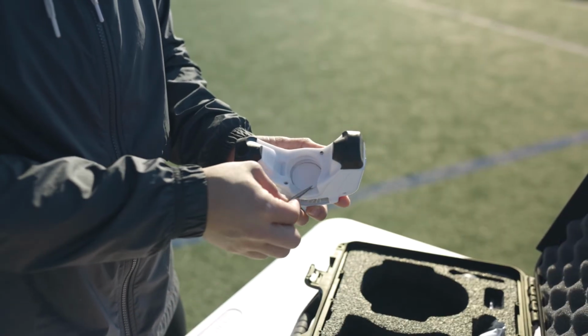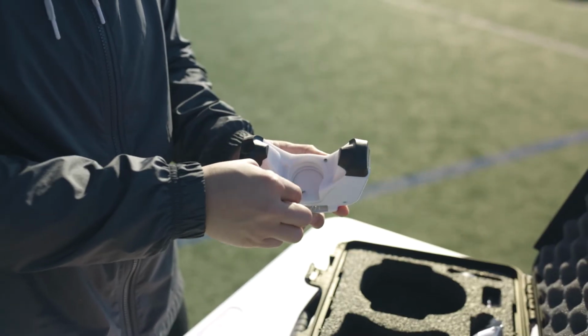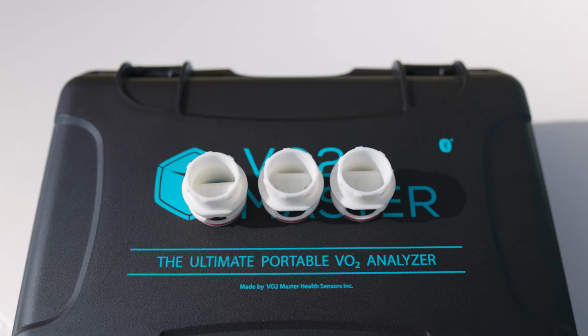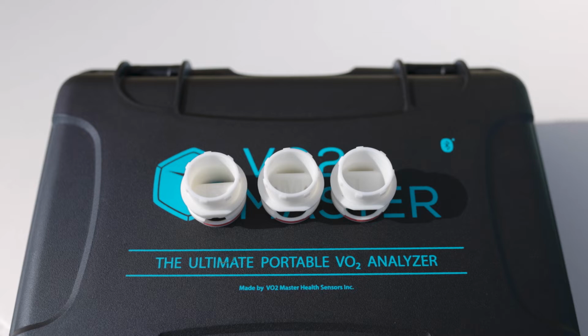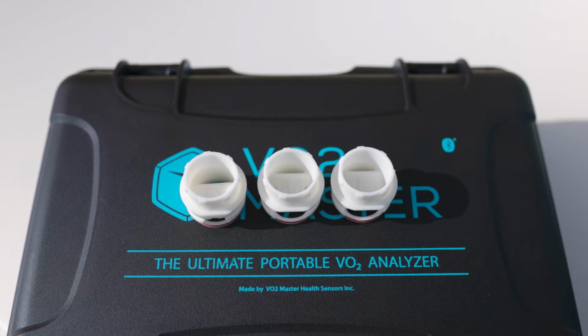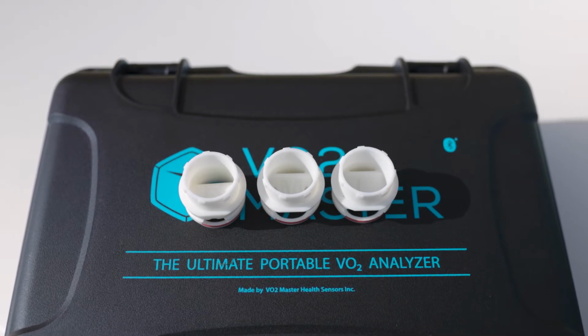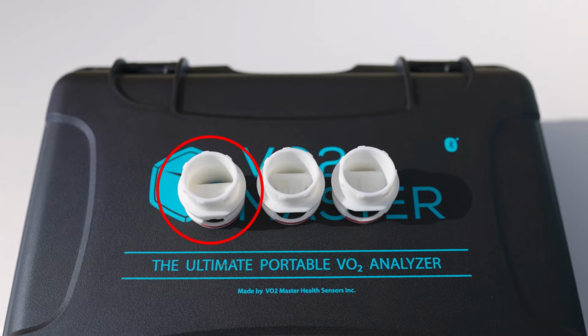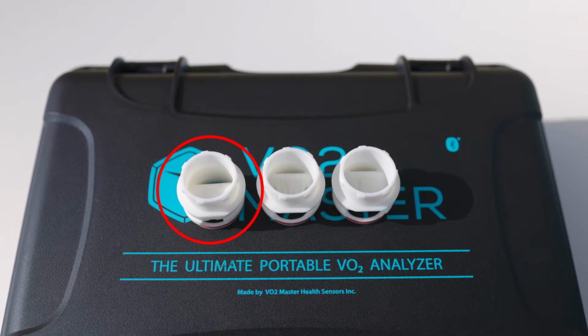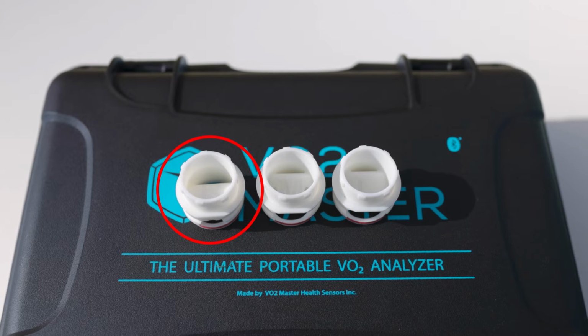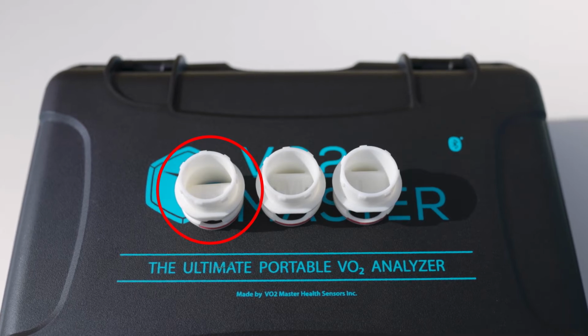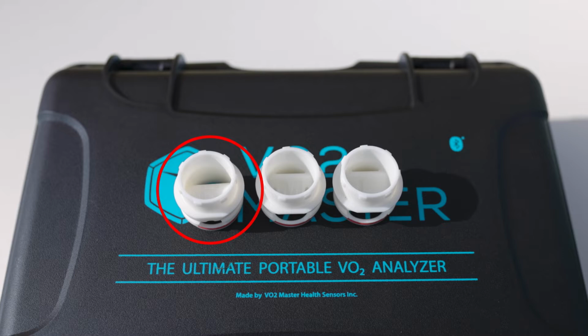Next, you will assemble the hardware by placing a clean filter into the VO2 Master Analyzer. They are reusable flow inserts, and each size is optimized for a certain flow range and application. The user piece indicated by the embossed letter R is used to test resting metabolic rate, which measures caloric expenditure at rest. The ventilation range is between 5 and 40 liters per minute.